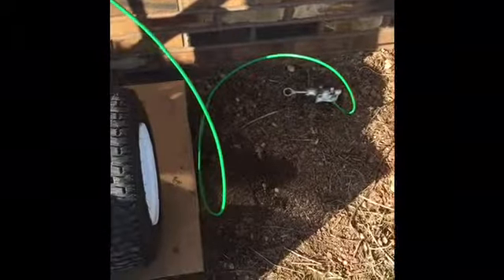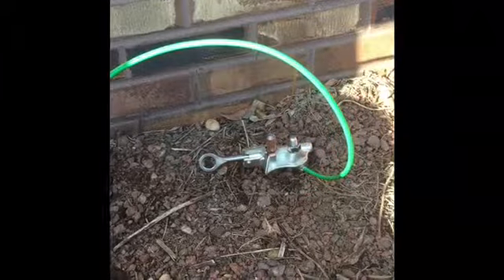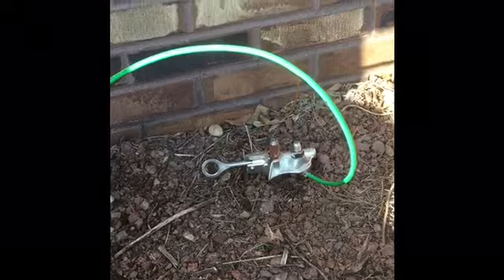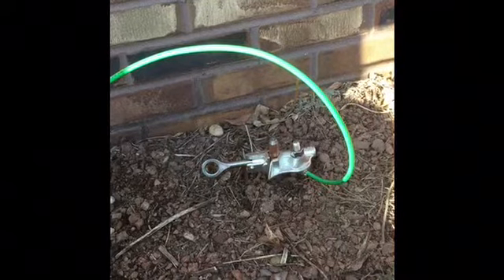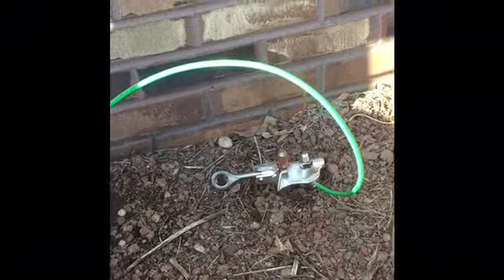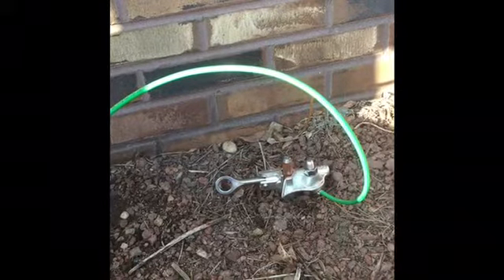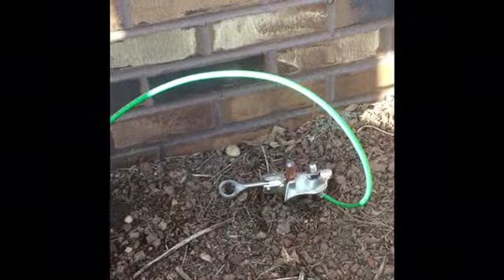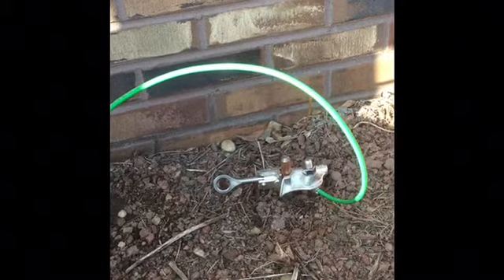Okay, and after we connect the neutral pigtail to the neutral bus bar in the meter socket, the next step is to connect our clamp that we have provided with the cart to a ground rod there. So as you can see, it's a live line clamp type setup, so it's an easy, quick connection to the ground rod there, and then you see the lead coming from the side of the breaker cabinet that's connected to a lug inside the cabinet there that grounds the cart.